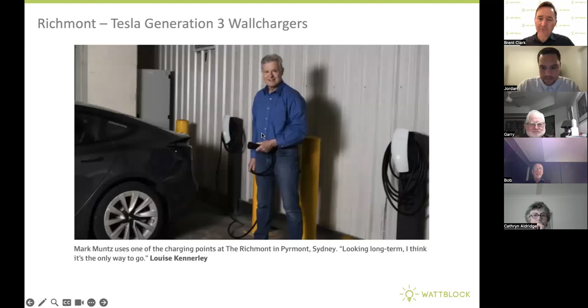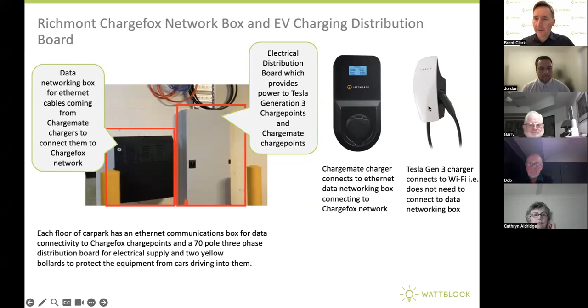Here are some visitor charge points, mounted on a bollard. Here's an example of a new distribution board, and here's a networking box that goes next to it if you're running data cables from the charge point into this networking box. There'll be 32 connection points, so you can have 32 charge points connecting their data cables into that. The Tesla system is Wi-Fi based, so it doesn't need the data cables.